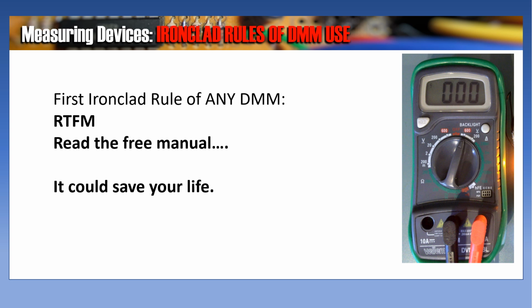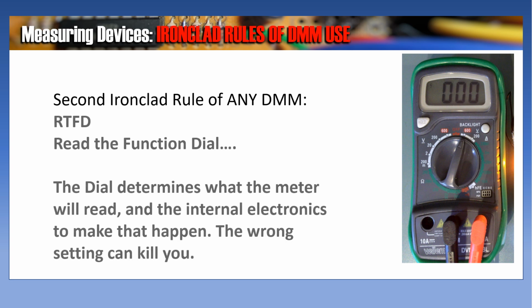Before we get too carried away with the differences between one model and another, we should discuss the ironclad rules of digital multimeter use. And the first ironclad rule of any digital multimeter is RTFM. Read the free manual. It could save your life. The second ironclad rule of any digital multimeter is RTFD. Read the function dial. The dial determines what the meter will read and the internal electronics to make that happen. The wrong setting can kill you.